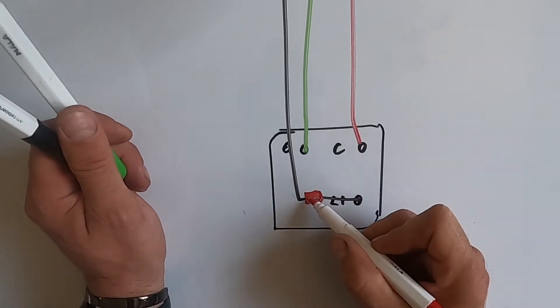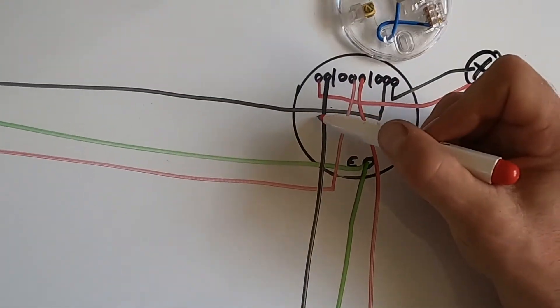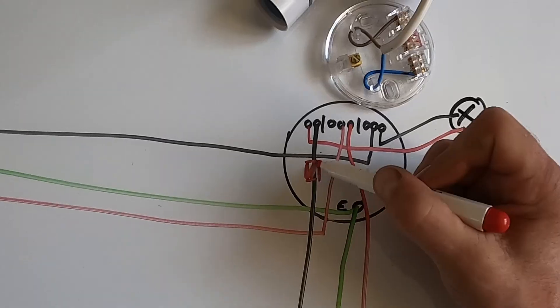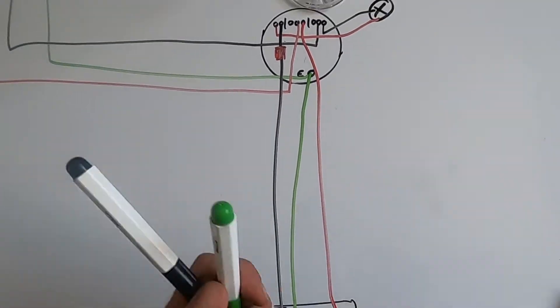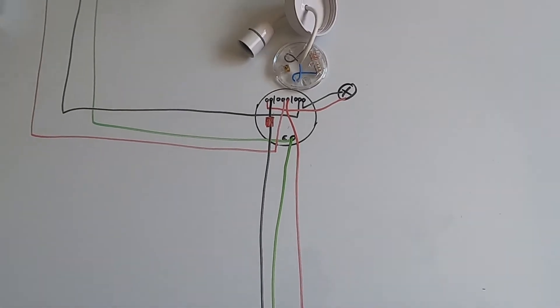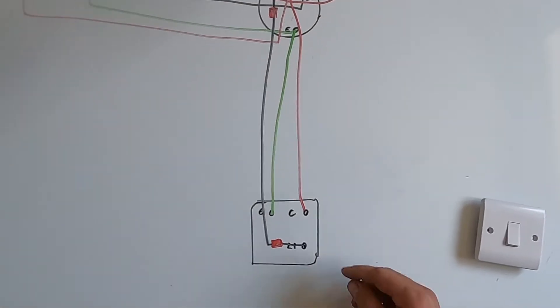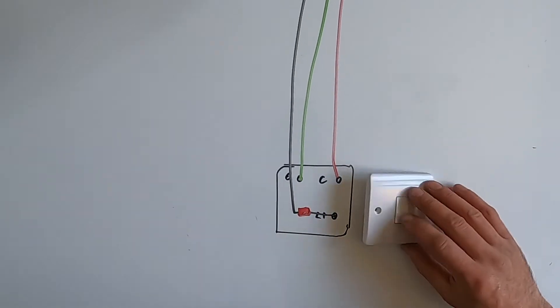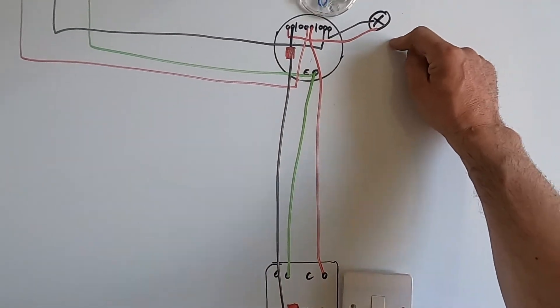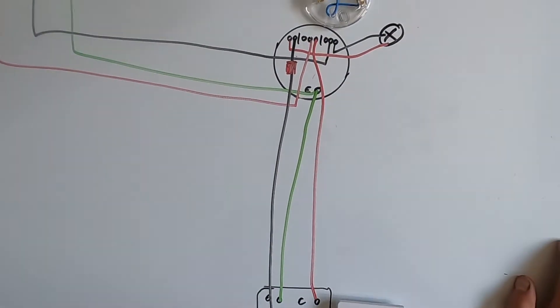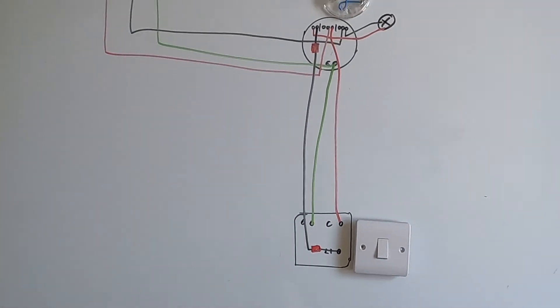In the switch where you terminate it, put sleeving on that cable. So that will be your lighting circuit switch, because then when you switch this on and off, it will switch the lives going to the light and obviously turn the light on and off. And that's how to wire a ceiling rose.